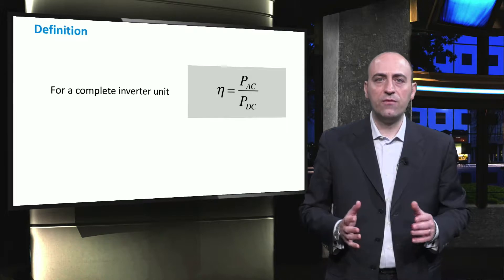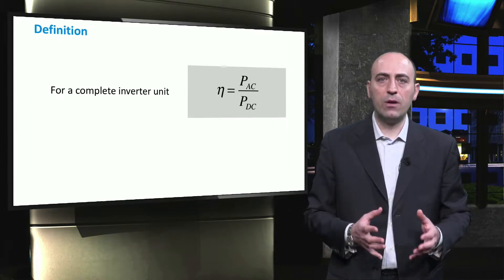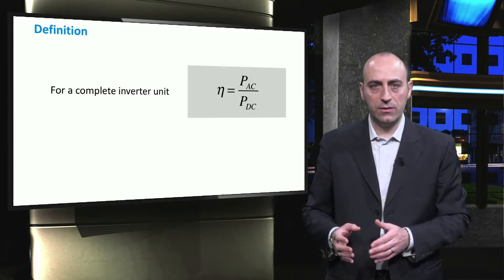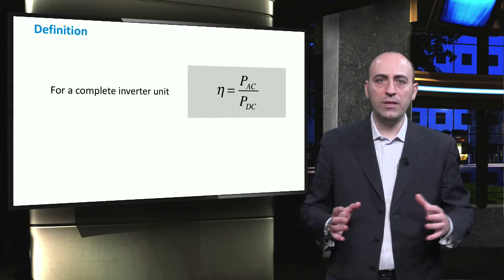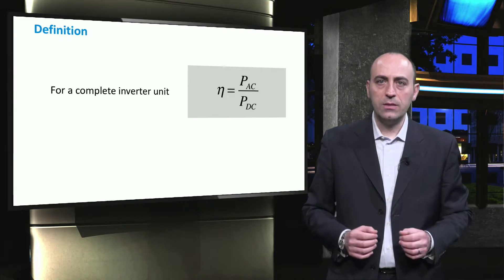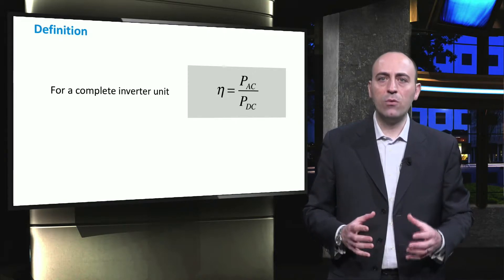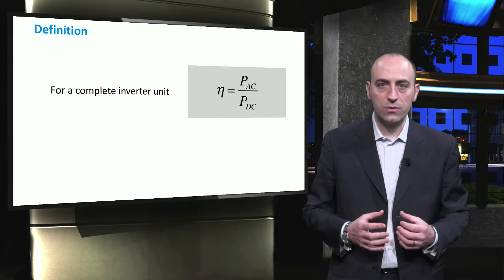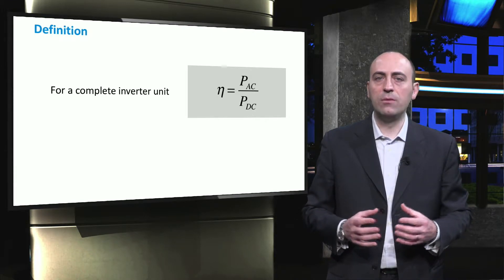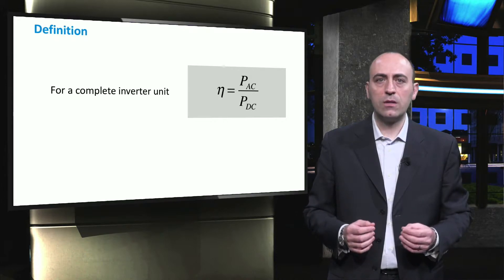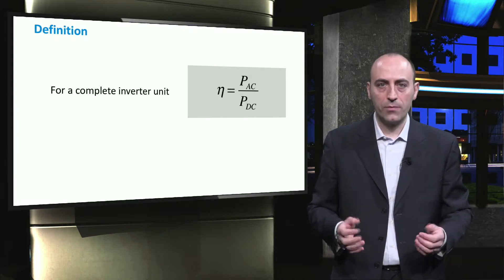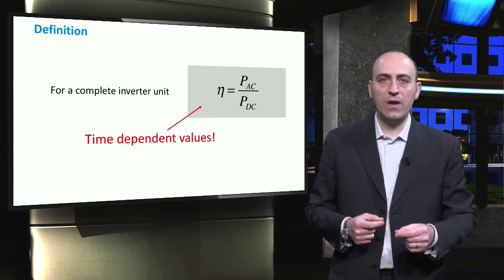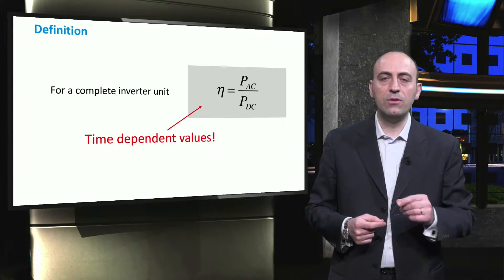The efficiency of the inverter is defined as the ratio between the power output at the AC side and the power input at the DC side. This definition comprises the complete inverter unit. Since the real inverter has many components and due to the lack of detailed data from inverter manufacturers, some models have been developed to describe the efficiency. These models are based on empirical formulas. It is important to note that the efficiency reported is an instantaneous value, which means that it is time dependent.